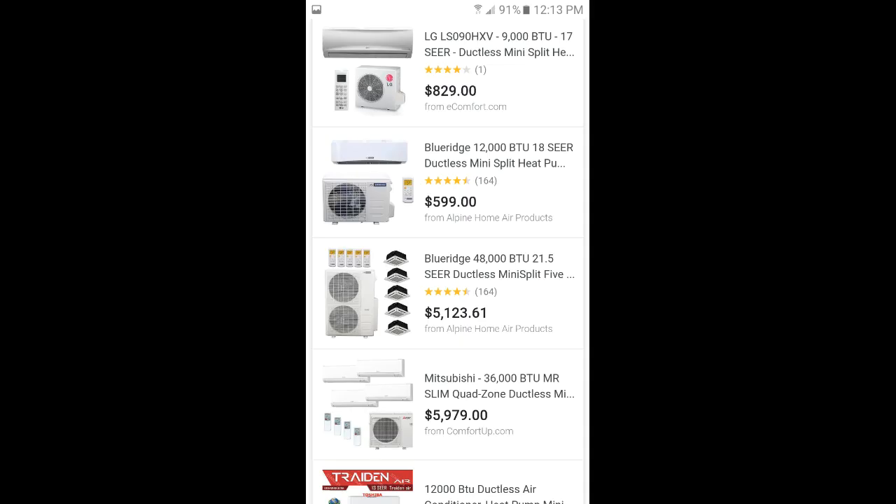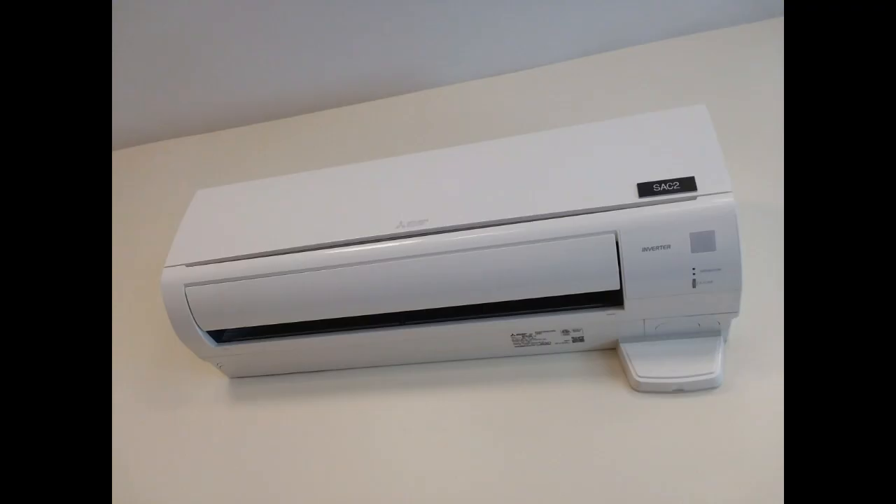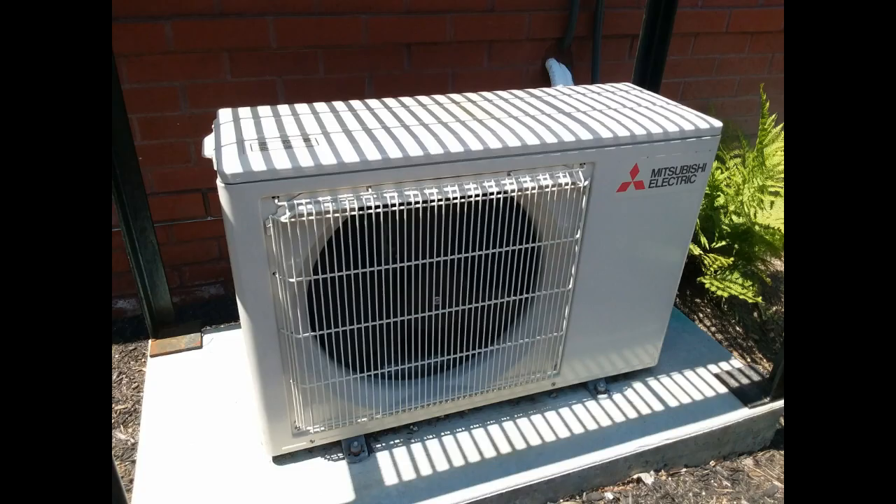You've got a wide range of coolant levels with a mini ductless split system, from 9,000 BTUs up to 36,000 BTUs. You're going to be putting a hole through your wall — a 2 to 3 inch hole is going to be drilled through your wall. The indoor portion hangs on a wall-mounted frame, and then the copper air handler wires and the plastic condensation tube are fed through that hole in the wall and attached to the heat pump condenser unit outside.